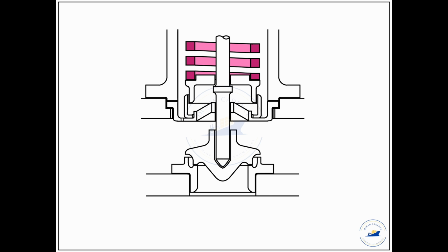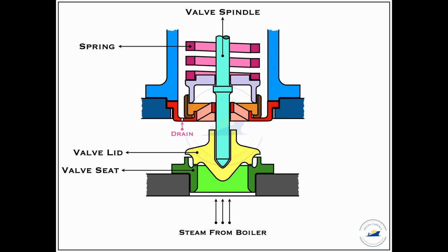It is also to be made sure that any passages, especially the smaller passages like the drain channel which are there on the body of the valve, have to be under open condition at all points of time.